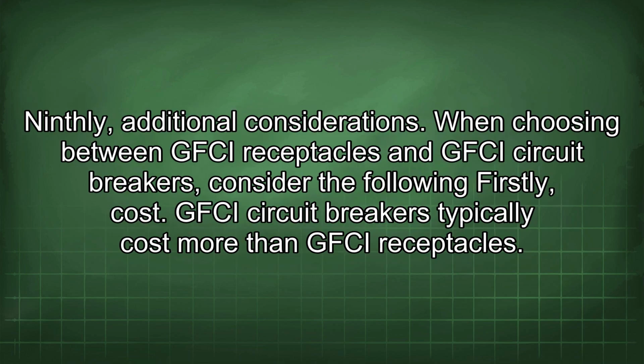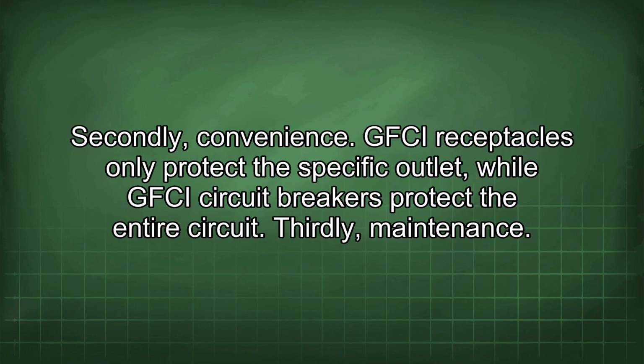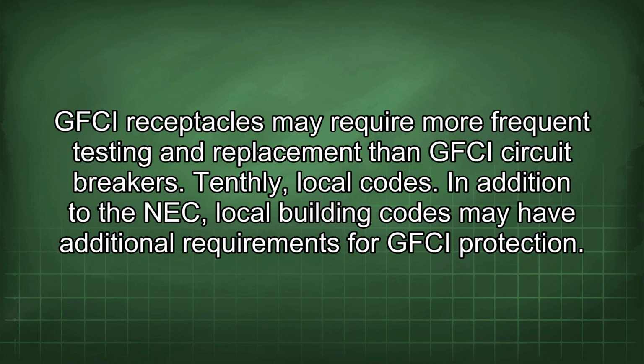Ninthly, additional considerations. When choosing between GFCI receptacles and GFCI circuit breakers, consider the following. Firstly, cost. GFCI circuit breakers typically cost more than GFCI receptacles. Secondly, convenience. GFCI receptacles only protect the specific outlet, while GFCI circuit breakers protect the entire circuit. Thirdly, maintenance. GFCI receptacles may require more frequent testing and replacement than GFCI circuit breakers.